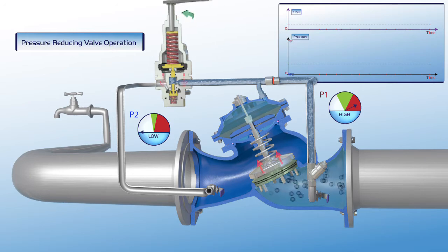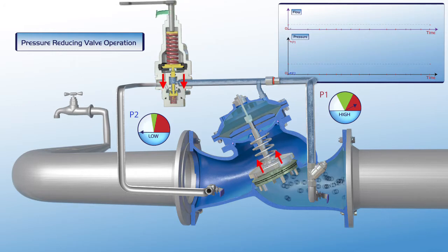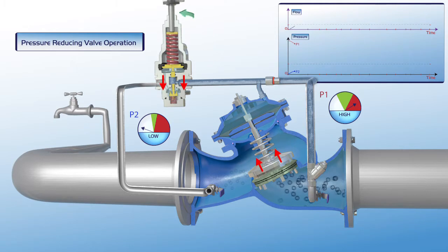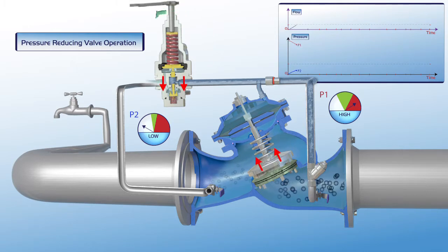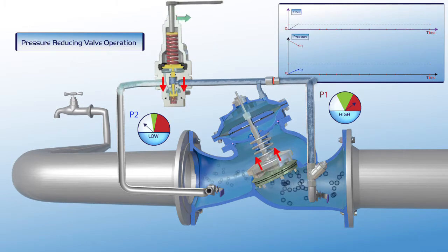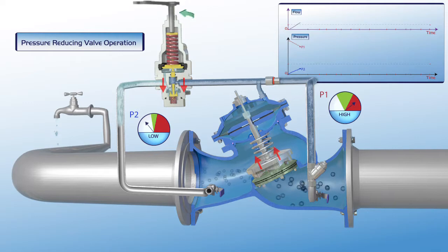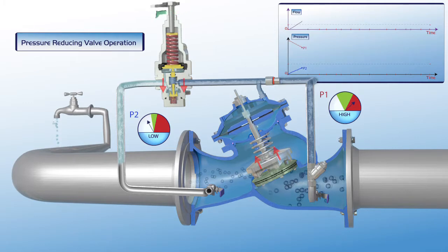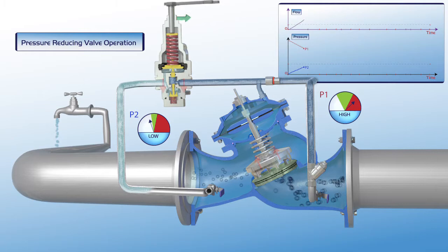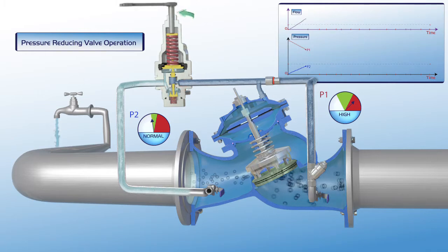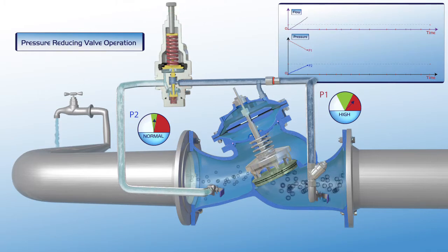The user gradually turns the pilot adjusting bolt clockwise. The pilot plunger is pushed downwards, causing a pressure drop in the valve's upper control chamber. This results in the gradual opening of the valve and filling of the consumer line. The downstream pressure stabilizes at the P2 gauge green zone.